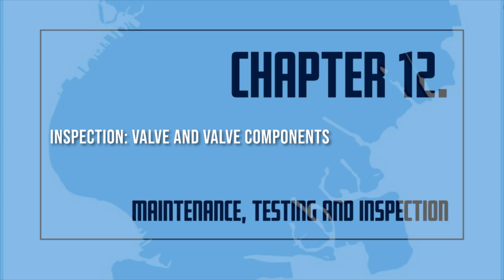The interior of the valve and the condition of detection devices shall be inspected annually when the trip test is conducted. Internal inspection of valves that can be reset without removal of a faceplate shall be permitted to be conducted every 5 years. Strainers, filters, restricted orifices, and diaphragm chambers shall be inspected internally every 5 years, unless tests indicate a greater frequency is necessary.